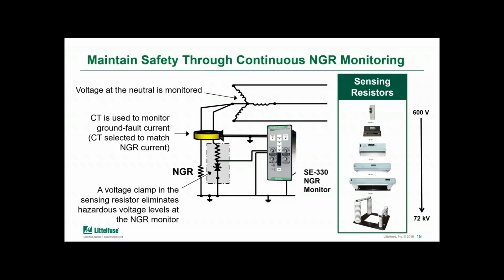Okay. And the other associated question is, does the NGR monitoring work the same on low resistance and high resistance grounding schemes? The monitors do work the same on high resistance or low resistance grounded systems, yes. Now, in the case of some of these relays, they need to be calibrated when installed and various set points put into the relay so it understands what type of resistance is expected and what type of resistance increase or drop is not acceptable. But yes, the overall design principle would still be the same for low resistance or high resistance grounding.